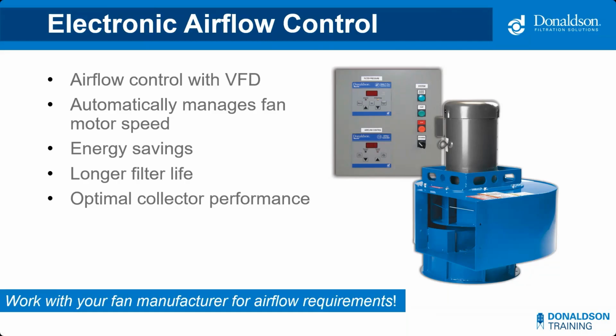When specifying an airflow controller with a VFD, it's important to work with your fan manufacturer to understand the airflow requirements. Often, they will recommend oversizing the fan slightly to allow for the maximum benefits of the VFD. Carla, can you talk us through a little bit more on electronic airflow control?